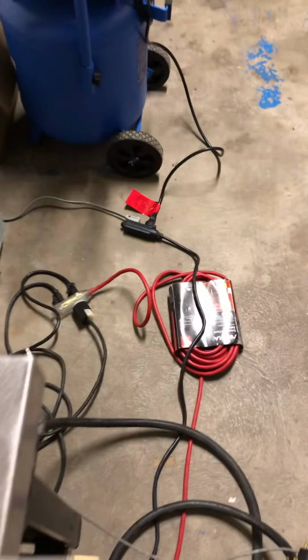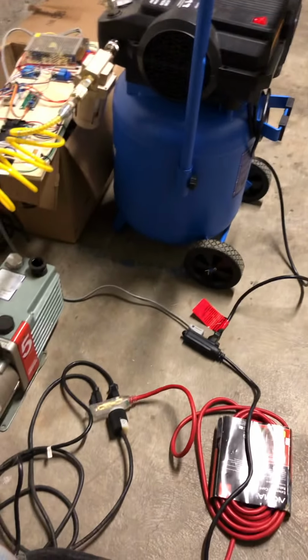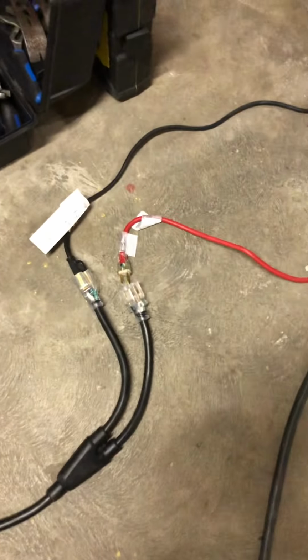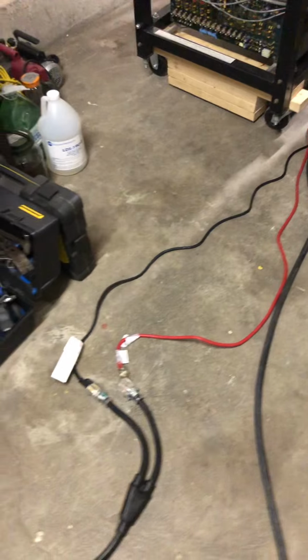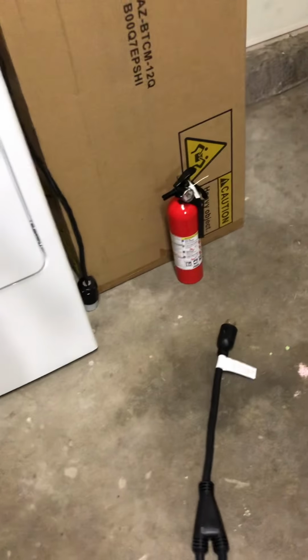And then from here we just have the extension cords going out to everything that's back here, which is the air compressor, the water chiller, and the 3 rotary pumps. And technically this isn't really that safe because everything downstream of this is going to be rated for only 20 amps. But if you follow up, this is going to go back to the panel, which is a 30 amp circuit. So you could actually get 30 amps onto this cable if your load was not acting properly. So this isn't really that safe, but I mean, I'm only going to be operating this when I'm in the room. And I guess that's why I also have the fire extinguisher ready and available to use.